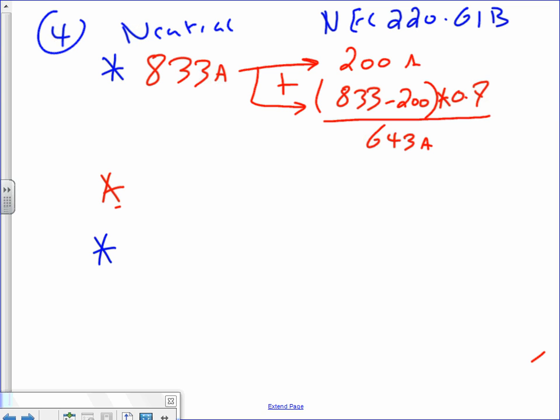The first 200 amps, leave them alone. What they do in this section, whom am I going to pick this time? So my friend, because for the neutral, guys, it is highly unlikely the equipment will be on at the same time, they allow you to derate the neutral even more. So how do you derate it? You leave the first 200 alone. So Jay, my friend, after you take 200 from your amps, cut the rest by what? 70%, and add them up. Everybody knows what this math, fuzzy math, is. First 200 plus the difference between these two multiplied by 0.7. I did them all in one step.